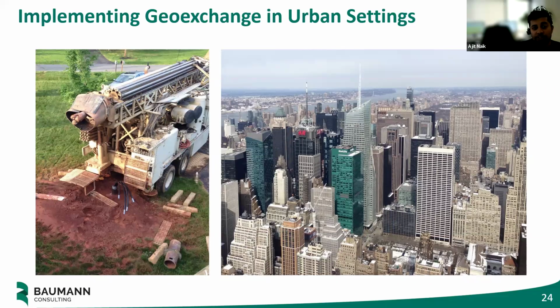It's really important in all geothermal systems, but especially in urban settings, where it's harder—your system might be under your building or under a parking lot, which is a huge pain, as opposed to a large open grassy field. It's really important to employ inspections, commissioning, a little bit of extra effort, ideally via third party, for quality controlling your installation, so the as-built condition truly matches the design intent.